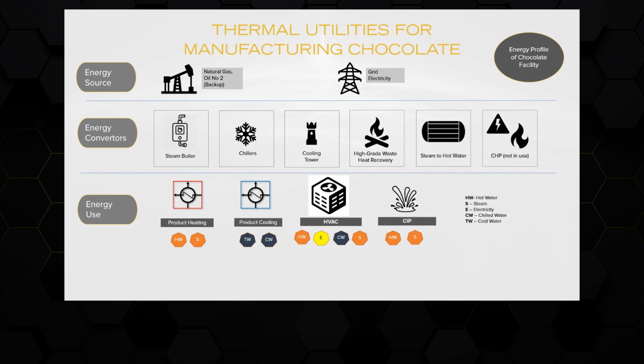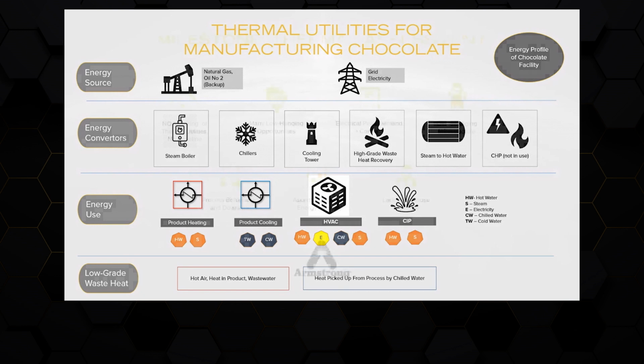So a central cooling tower plant recirculates water to equipment. One of the two steam boilers has an economizer, which can recover heat from the stack, but a significant quantity of low-grade waste heat was available in the form of cooling water or wastewater.